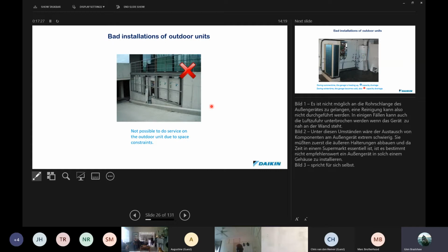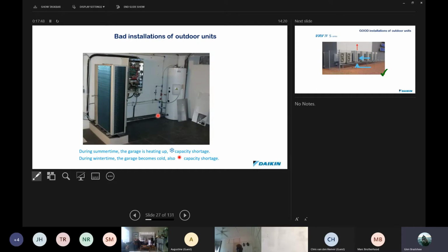Something else about the installation of outdoor units that we need to consider, okay, is that we must allow access around the units for servicing. Okay, and as you can see over here, okay, this does not allow for good access to the servicing of the units. Okay, moving on from that, mounting or installing units in confined areas is not advisable. We must make provision for the discharged air from the condenser to be moved away from the unit, and that it cannot be allowed to recycle and influence the unit or any other equipment that's in the room. During summertime, the garage will heat up and there'll be a shortage of capacity and cooling. And in the wintertime, the garage will become cold, and this will also reduce the capacity and heating.